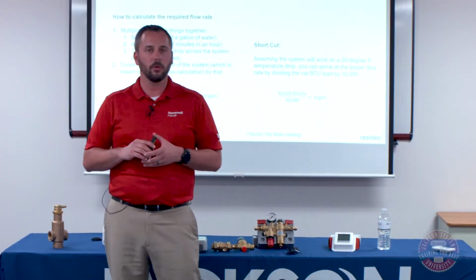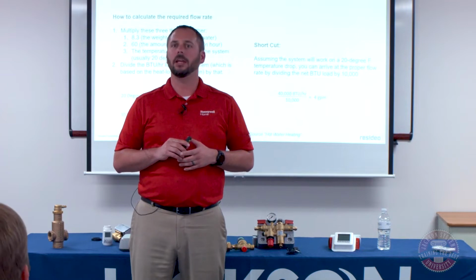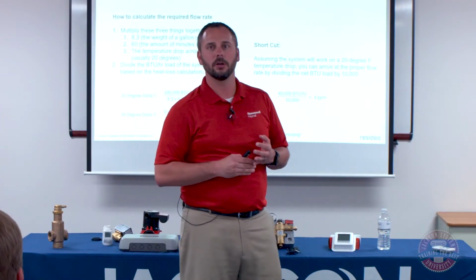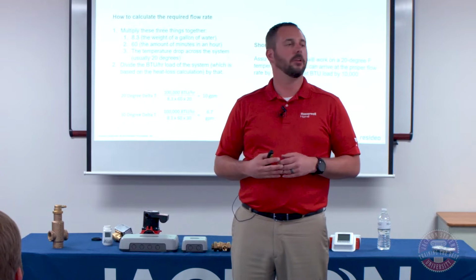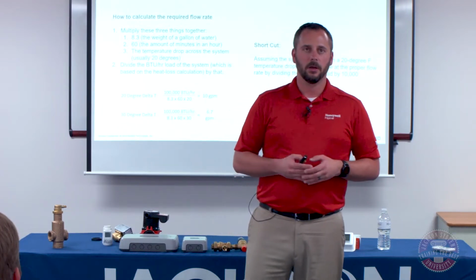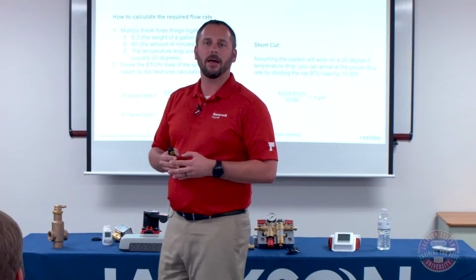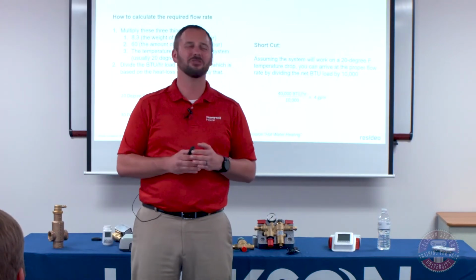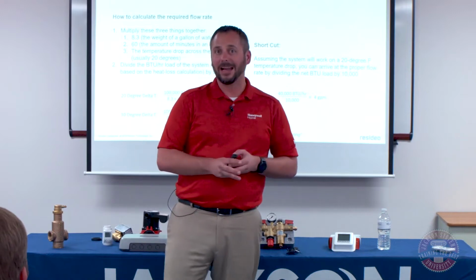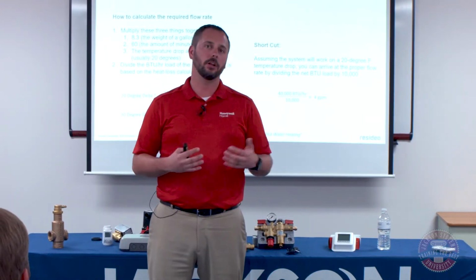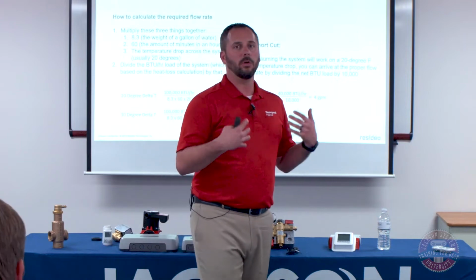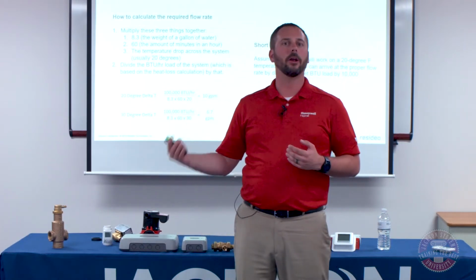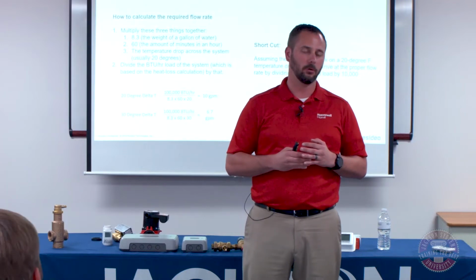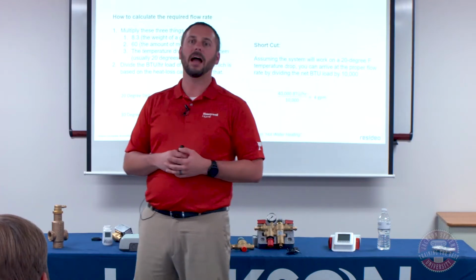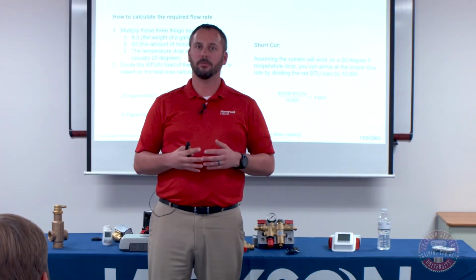So in order to come up with the flow rate, it's going to depend on your delta T. Delta T is just change in temperature. In the US, we have pretty much adopted a 20-degree temperature differential. I believe we have done that because the math is incredibly easy. So I'll go over that shortcut here in a minute. But when I was designing systems, a lot of times I would design it for a 30-degree delta T. Part of the reason being, with modulating and condensing boilers, you want to bring the water back to that boiler as cold as possible. So if you did a 30-degree delta T instead of a 20-degree, you typically brought the water back about 5 degrees cooler. It didn't move as fast, but you brought the water back cooler.